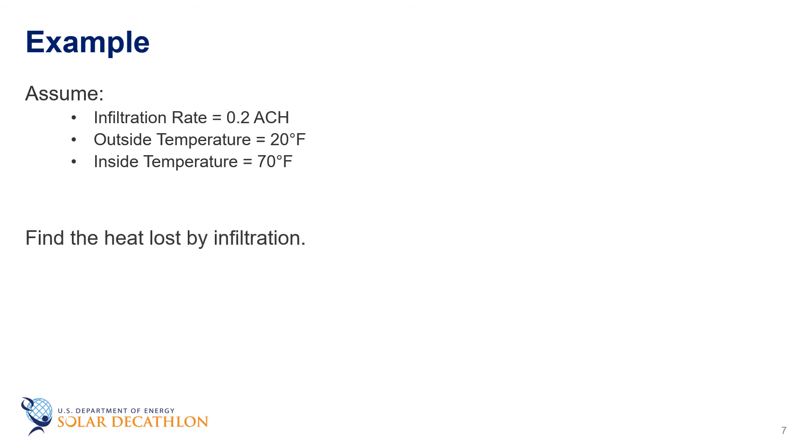Now, let's look at another example. For a building that has a leakage rate of 0.2 air changes per hour, the outside temperature is 20 degrees Fahrenheit and the inside temperature is 70 degrees Fahrenheit, let's find the heat lost by infiltration. Note that we generically call it infiltration, but it's really the amount of energy required to heat the infiltration air or the amount of heat lost by exfiltration. And let's say that the building contains a volume of 10,000 cubic feet.